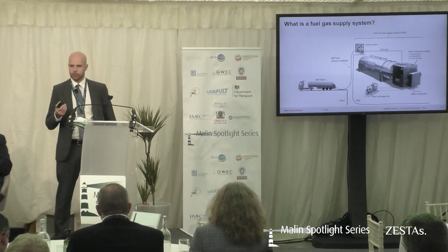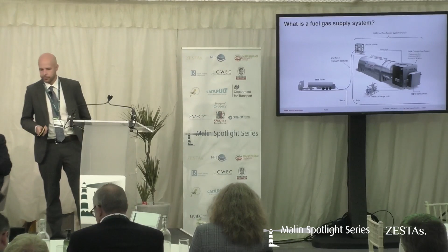So this component, this equipment, the function of it is to supply hydrogen to the consumer at the correct temperature and pressure. The design principle for a liquid hydrogen fuel gas system is that we receive hydrogen transported into the pressurized storage tank. We store the liquid hydrogen inside the tank at a slightly higher pressure than what is needed at the consumer. So if we have a supply to a fuel cell that requires 3.5 bar gauge inlet pressure, we store this liquid slightly higher than that.